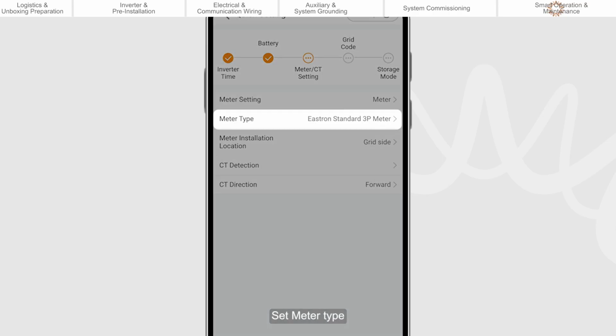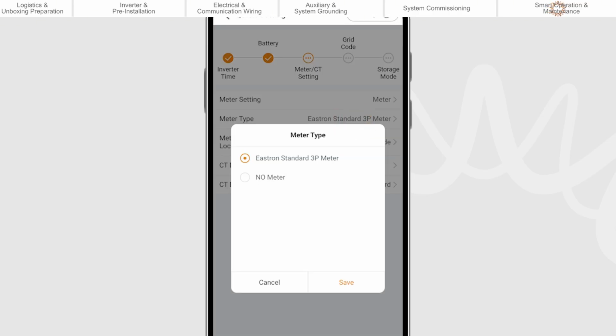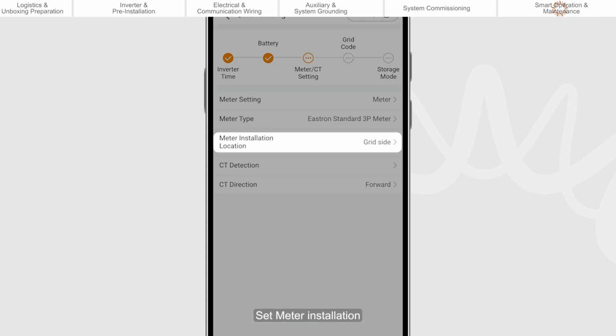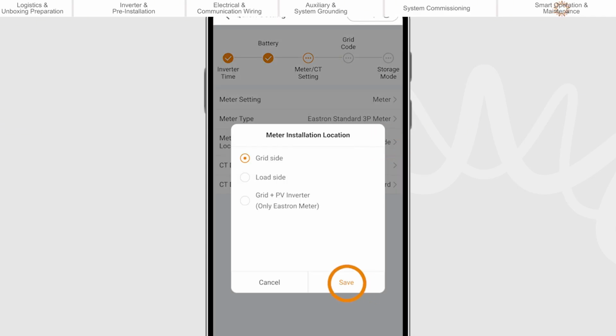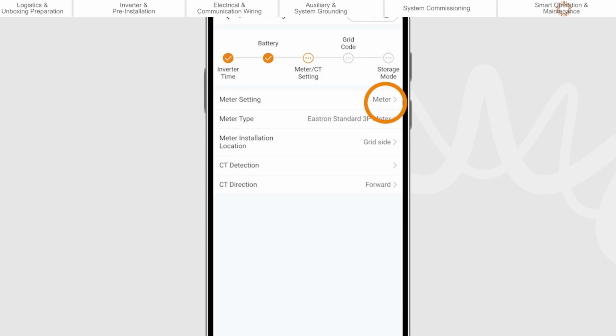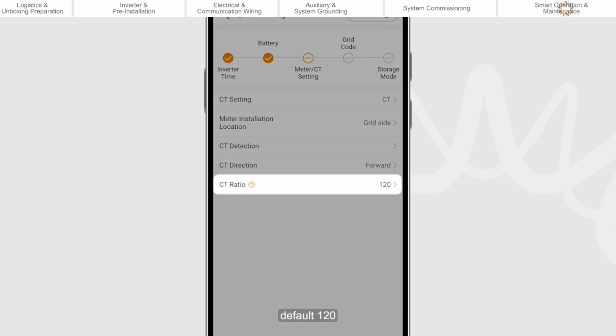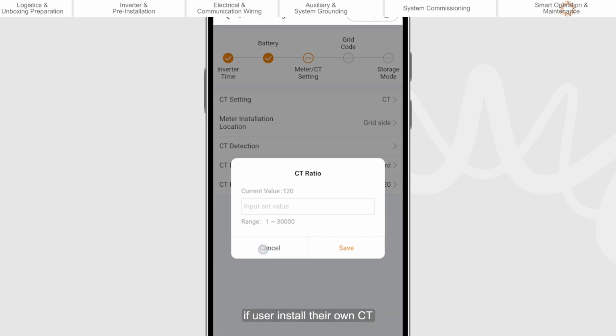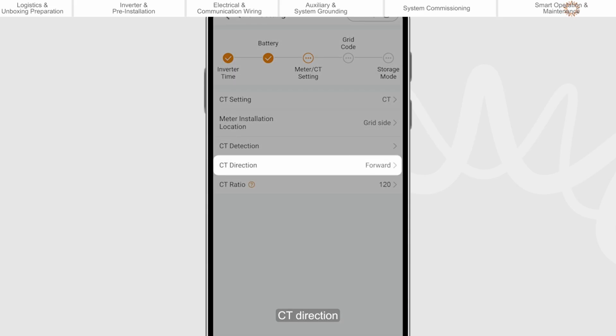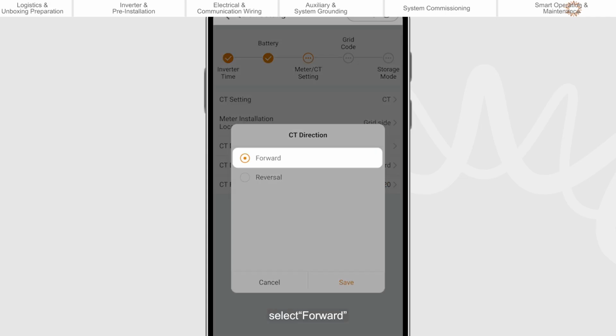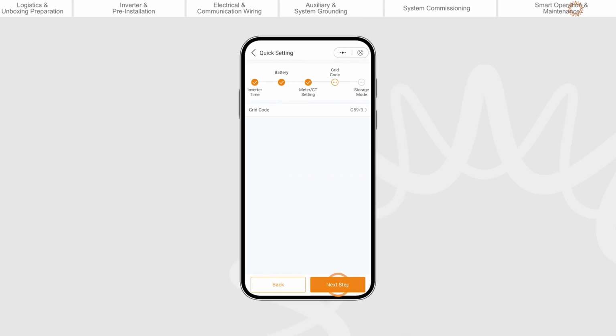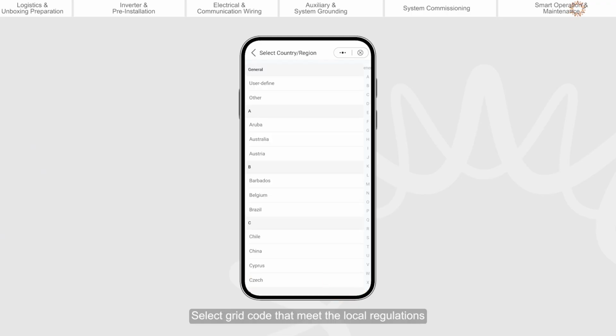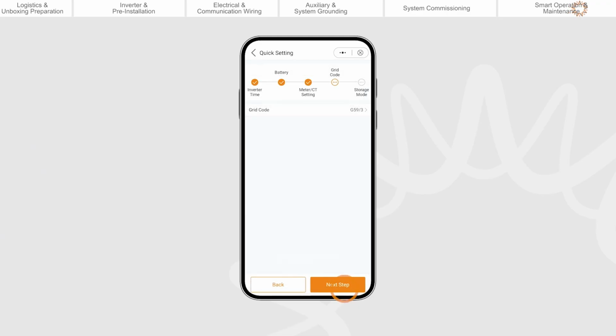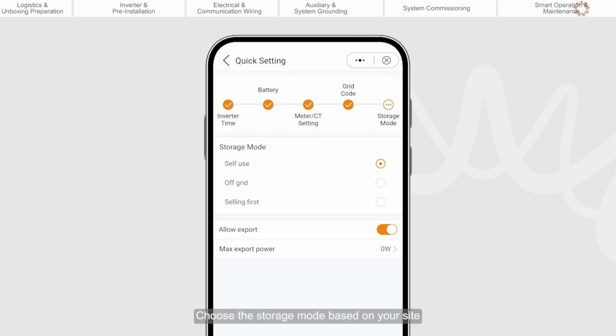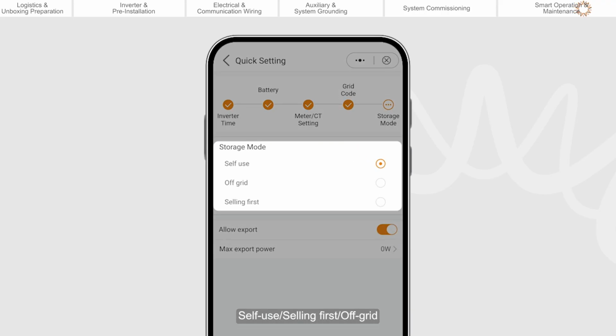Select meter. Set meter type. Set meter installation. Set CT ratio. Default 120. If user install their own CT, they need to set CT ratio manually on app and meter. CT direction. Select forward. Select grid code that meet the local regulations. Choose the storage mode based on your site, self-use, selling first, off-grid.